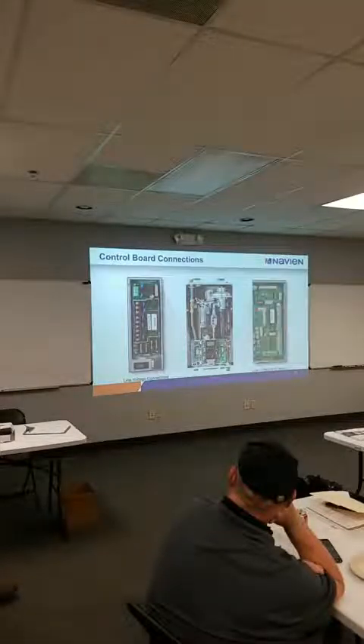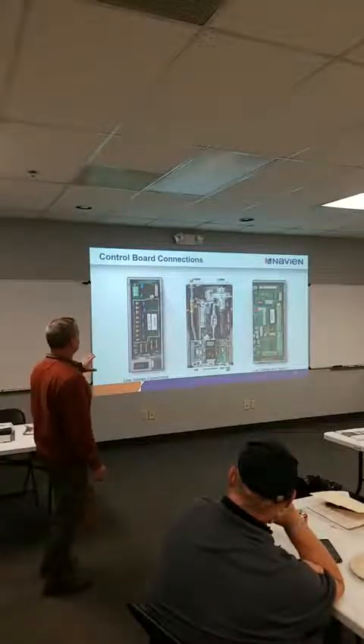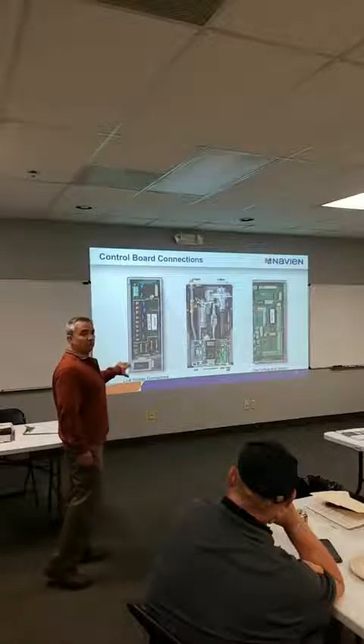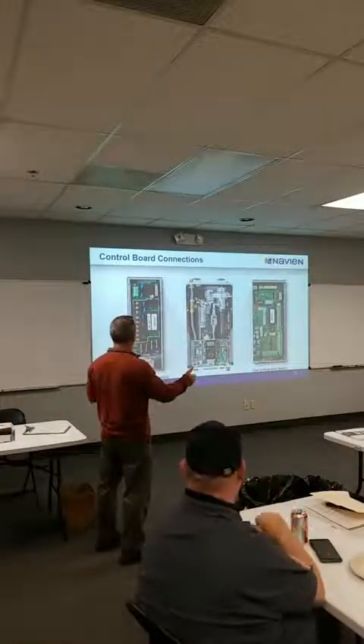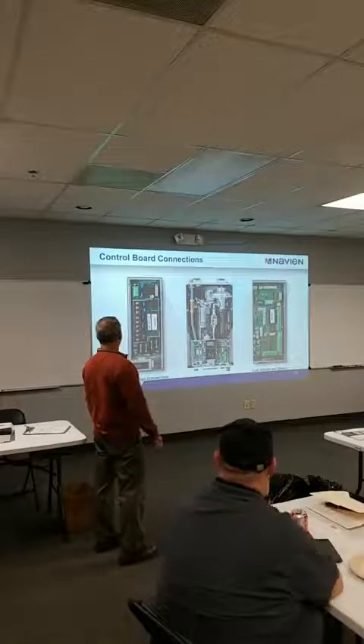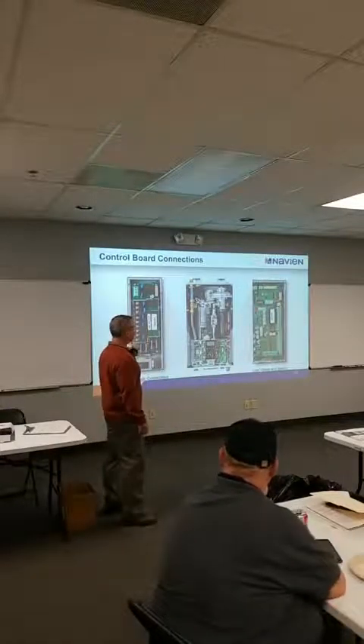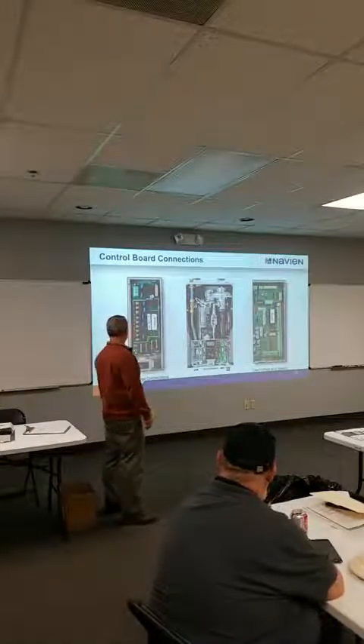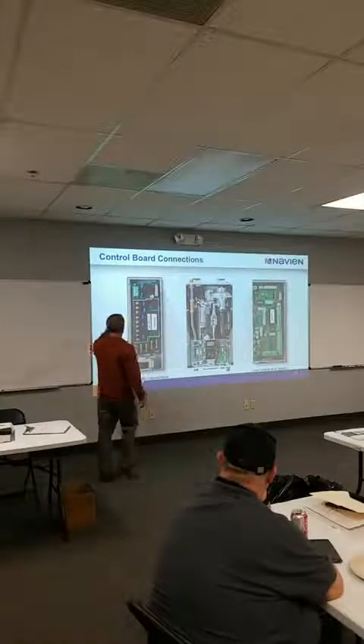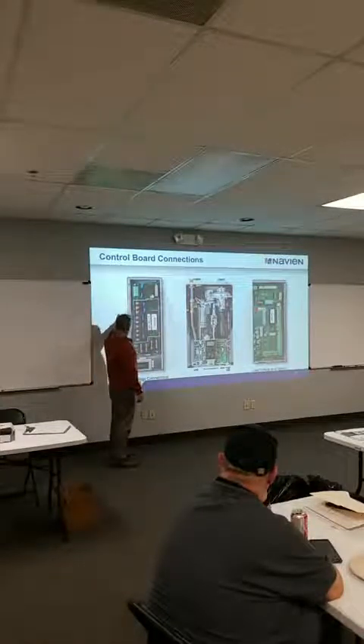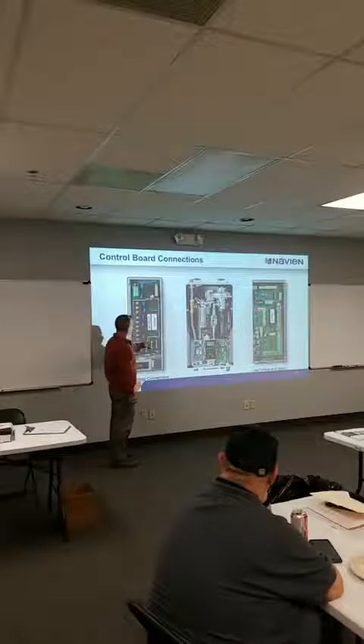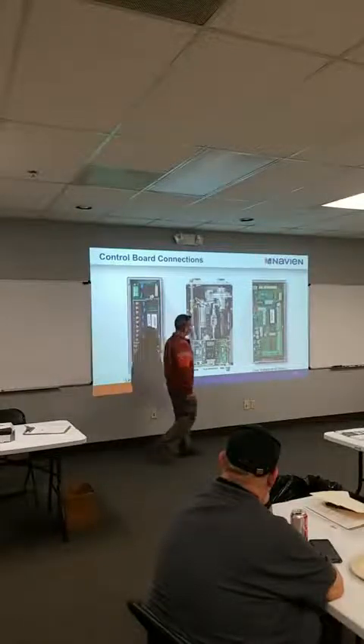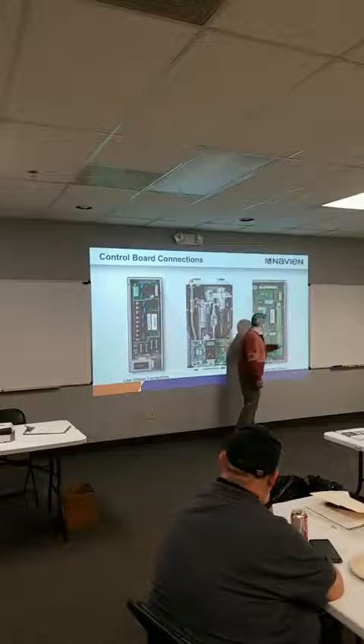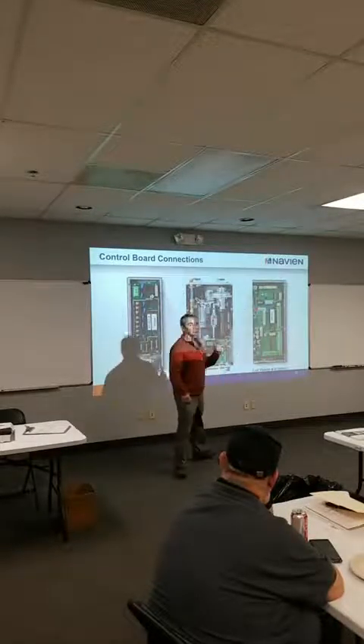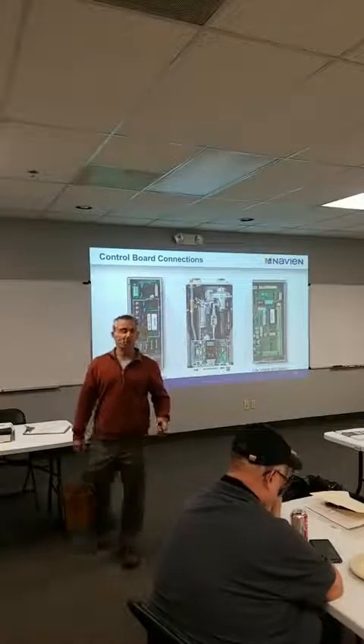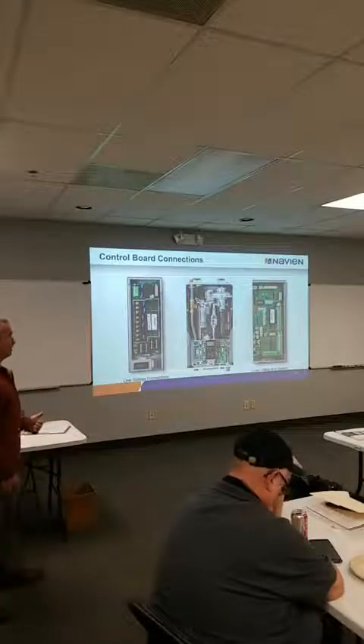So this is the new electronics board. It was standard with the NFB, but we're putting it in all the new equipment. It's gonna be the same board in all the equipment moving forward. You have a high voltage side and a low voltage side for this board. So you have your air handler connections, then we have pump connections here. They're all fused. On the other side, you have sensor, thermostat connections, and then other zone valve connections all the way to the right there.